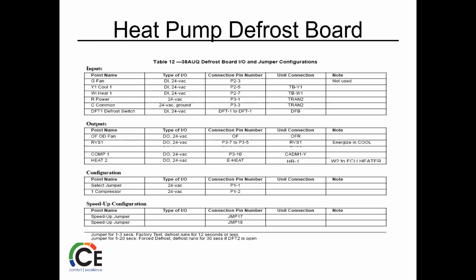So that board, this is off a 38 AUQ defrost board. It's kind of your ins and outs on some of those. Obviously GFan is a DI input, so it's just 24 volts. R power, ground, defrost switch is a 24 volt switch, and any defrost switch can be jumped out. It's just a switch, right? So if you're not sure, jump it out and see what happens.